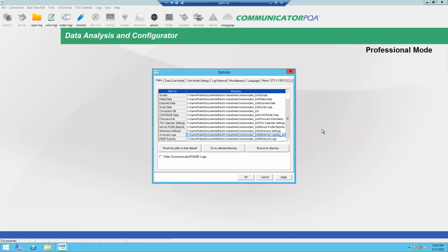A key part of this is your meter names. I'll show you how to do the automatic logging, but we won't set it up today, because the first thing you want to do is sort through your meters and find out if they're all named properly. What it does is take the meter name, also sometimes called the device designation, I think is the term they use in the setup. They use that as the file name that the log database will be recorded under, and you don't want to try to change that after it's already started. So we won't set that.